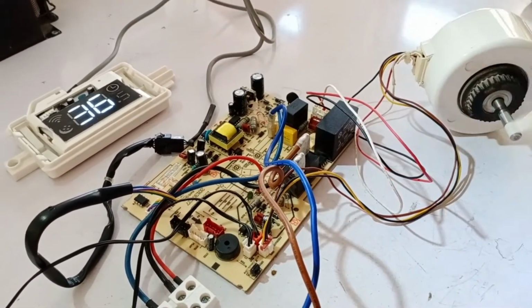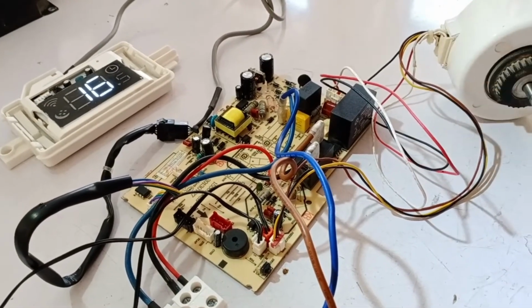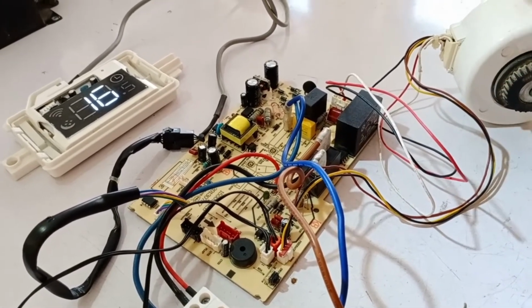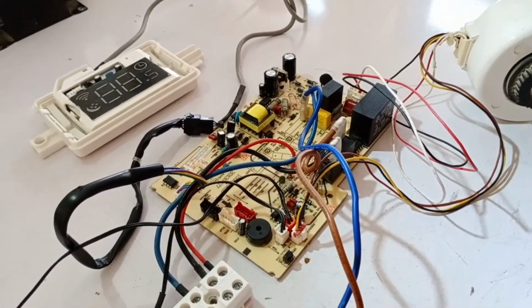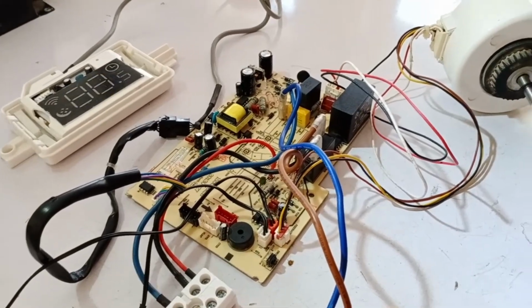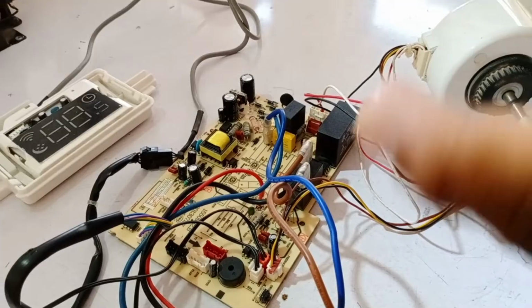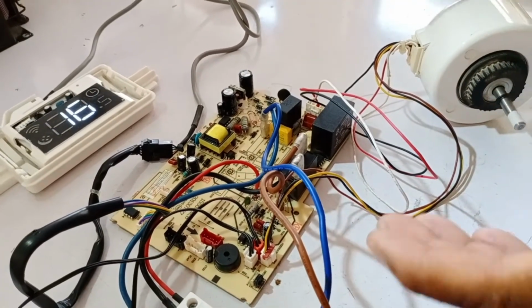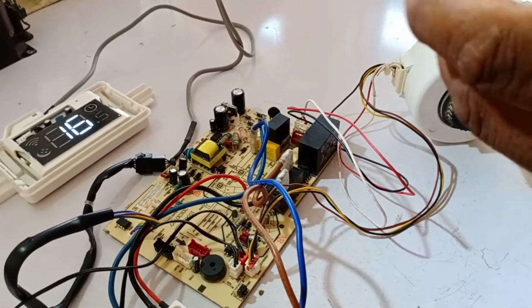4. Faulty outdoor PCB. If the fuse is okay, but the outdoor unit still does not work, this indicates that the outdoor PCB is faulty. A component on the outdoor PCB might be damaged, causing error 36. You need to repair or replace the outdoor PCB to eliminate the error. Once the fault is fixed, the error 36 will disappear from the display, and the unit will return to working condition.